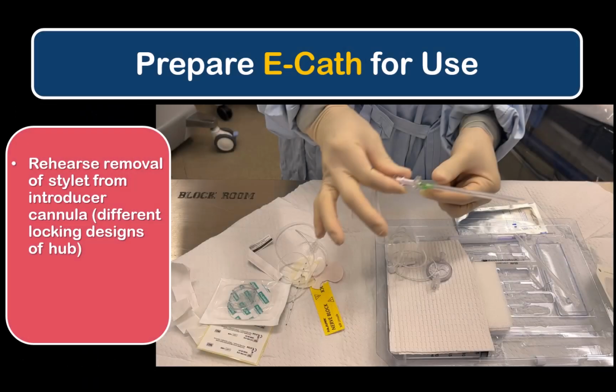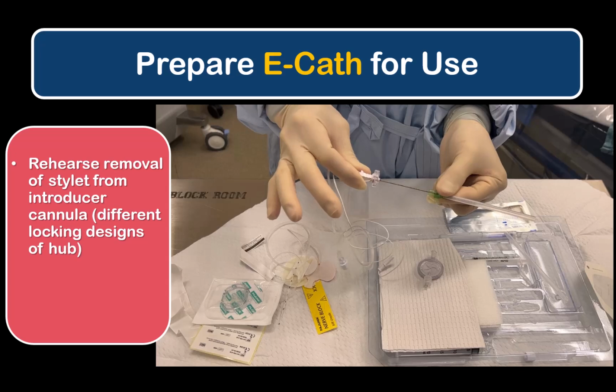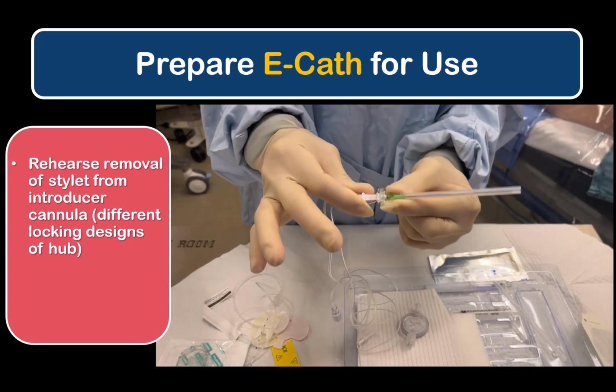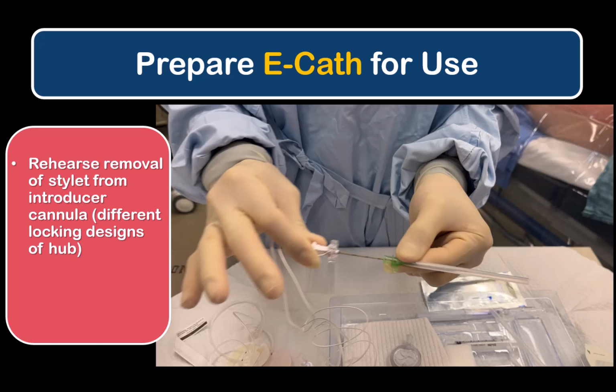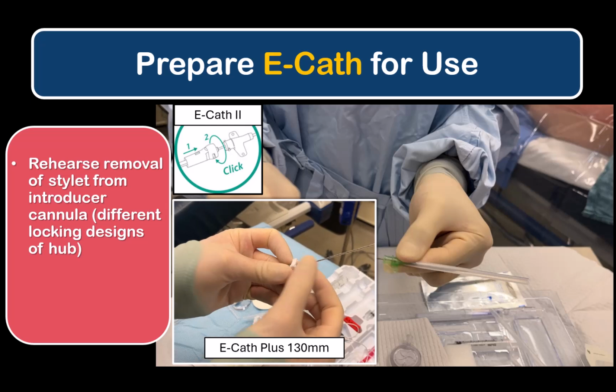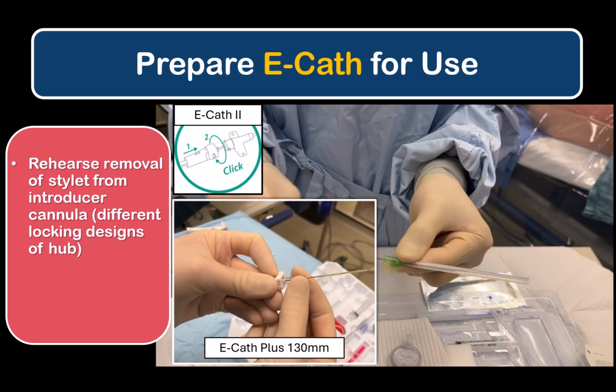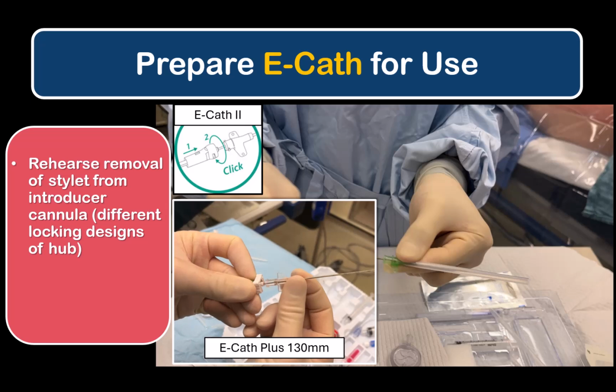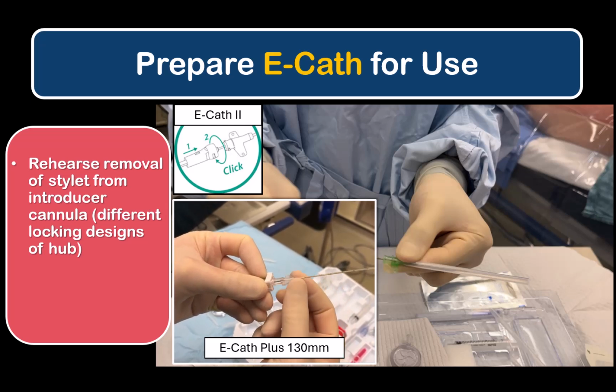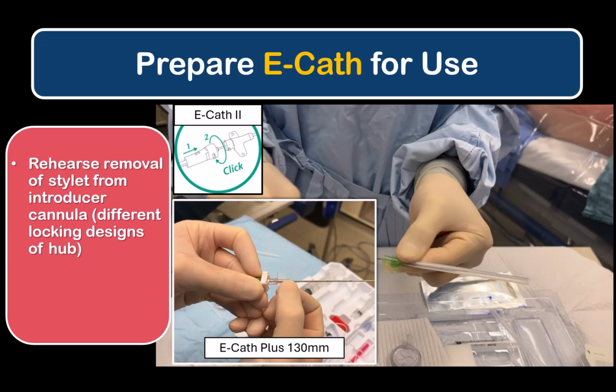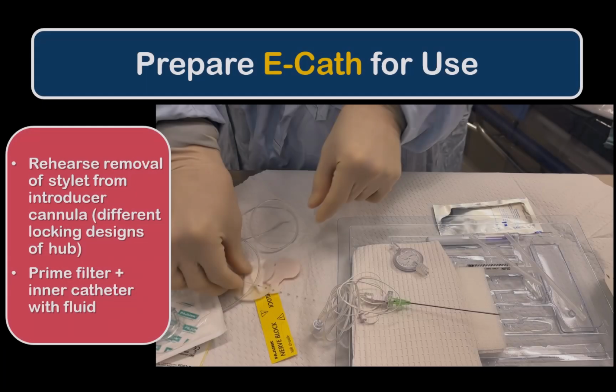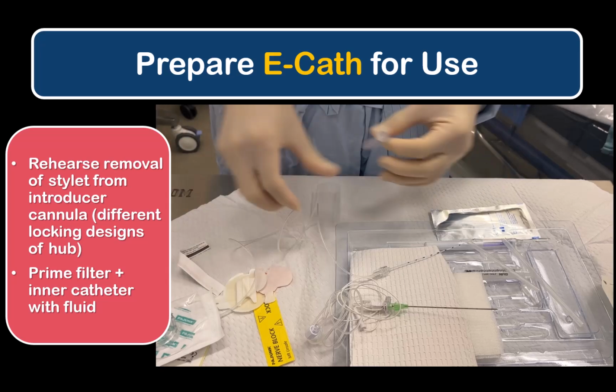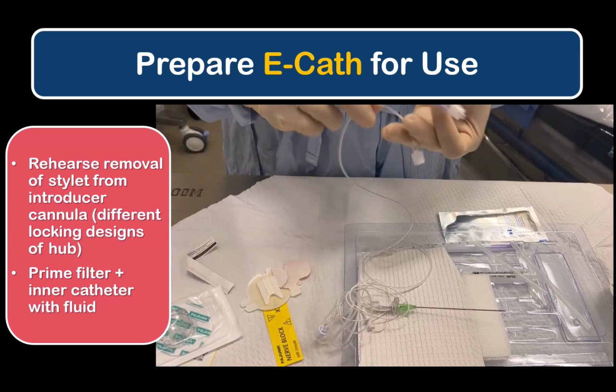As part of preparing the catheter set for use, you should familiarize yourself with how to disengage the stylet needle from the introducer cannula. First generation E-Caths require the stylet hub to be rotated 90 degrees to disengage from the cannula hub. Newer E-Caths have different hub designs, and some may require an unscrewing motion of a full turn or more, as shown. Attach the supplied filter to the hub of the catheter tubing and flush the entire assembly clear of air.